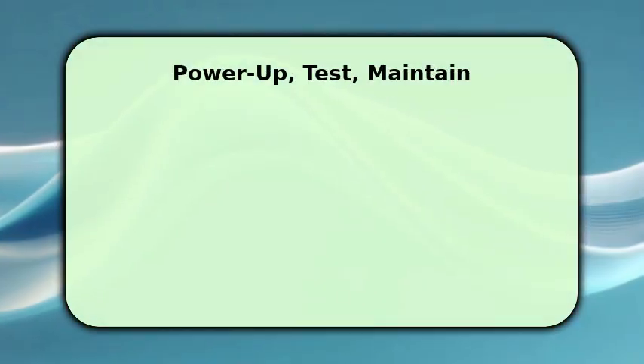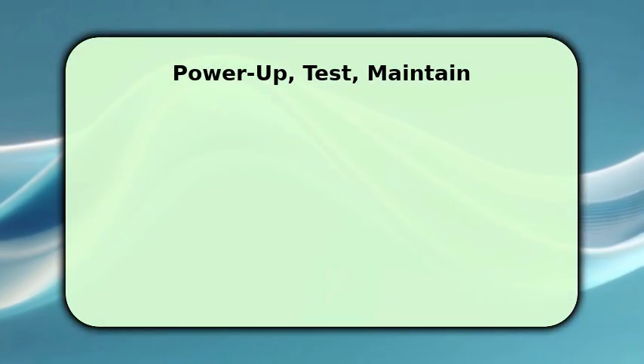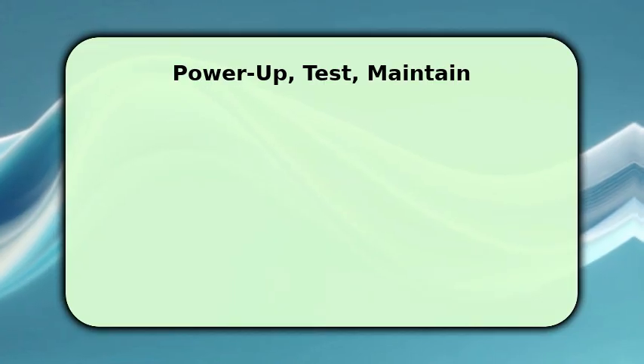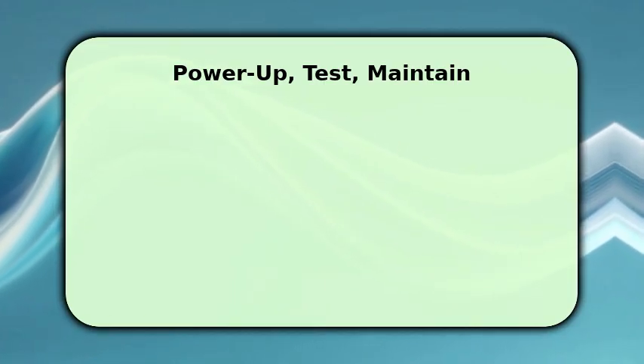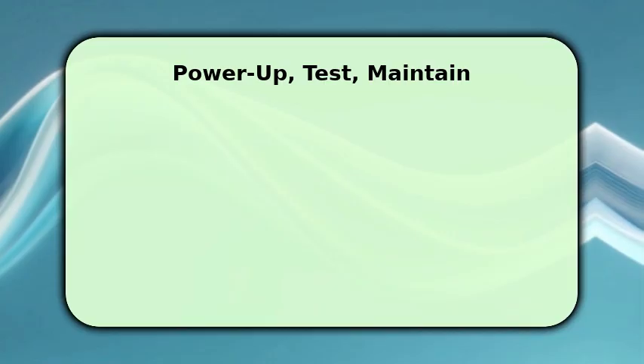Power on the stabilizer and verify output voltage reads within plus or minus 3% of nominal under no-load conditions. Apply the load gradually while monitoring voltage, current, and temperature, stopping if any reading exceeds rated limits.